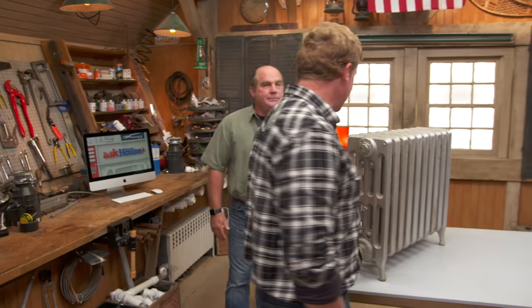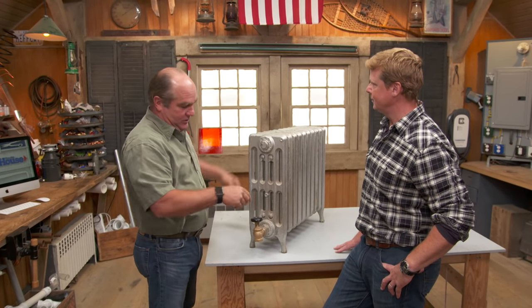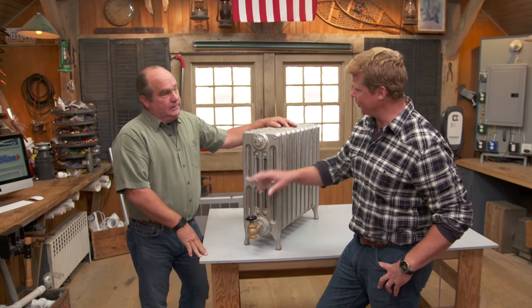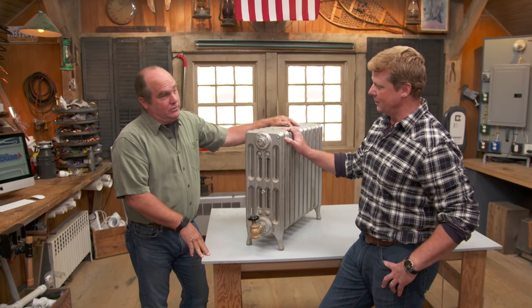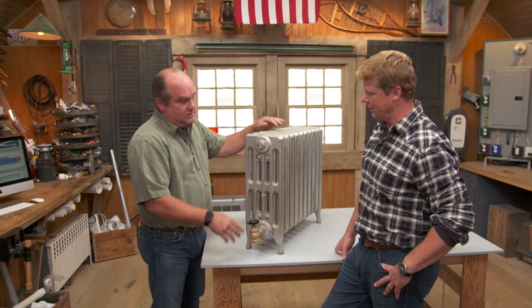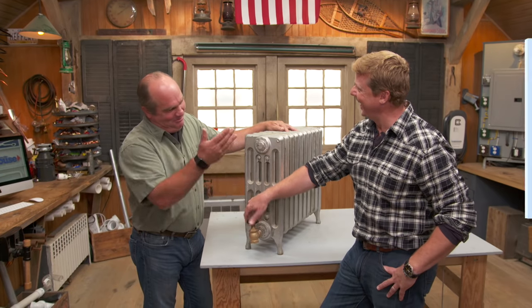Why do you think somebody turned that radiator off? The radiator was at the base of the stairs, so I assume all the heat was going up to the top-floor hallway, and the previous owner temporarily closed it off — effectively primitive zone control. So you made that house call all the way out there, and that was the fix? Yeah, on this one. But it's a reminder: don't overlook the simple things. I'm always called when things don't work and you assume it's some elaborate mechanical problem. It was just simple pilot error.